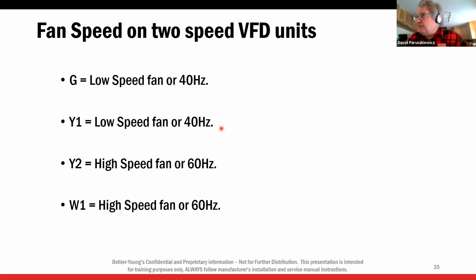Now, the VFD is capable of a lot of different things. We're only doing 2-speed with this. Now, you may work on some big rooftop units where we do full variable speed. We're not doing that. This unit's not designed for that. This unit's designed for 2-speed.